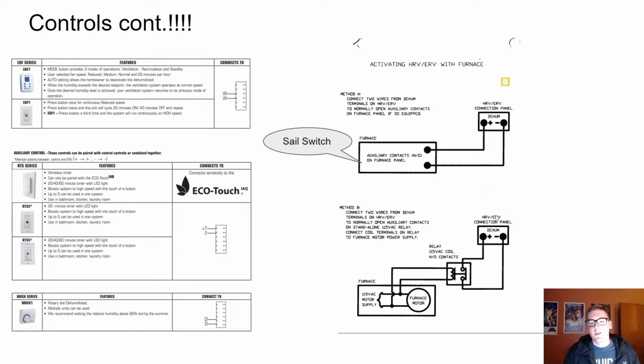And so this bottom option here was connecting a relay to the power supply on your blower motor, but because I have a variable speed blower, that gets a little more complicated. I wasn't about to go splicing into my expensive new Carrier furnace, so I didn't want to go with that option. And so the second option here was if they had auxiliary normally open contacts on the furnace that close when the fan comes on. So I didn't have that either, but my dad gave me a really good idea.